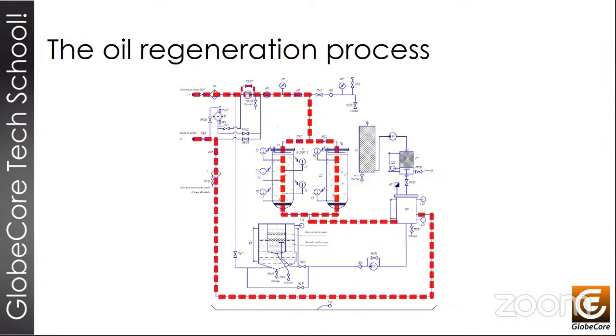Okay, the process usually consists of equipment that passes the oil through the absorbent. That's pretty straightforward, nothing special to it, right? But what makes it really interesting is that we have equipment that can reactivate the sorbent many times when it becomes saturated with contaminants. The way it's done is we burn the contaminants that are trapped in Fuller's earth. And to prevent environmental pollution from this burning, we also have special filters and catalysts. There are different machines. As a rule, what we manufacture ranges anywhere from 2 columns to 24 columns. It can actually be more, and it all depends on client requirements. This is a rather specialized piece of equipment, but using it will improve the oil in the transformer practically to as good as new condition. Next, please.